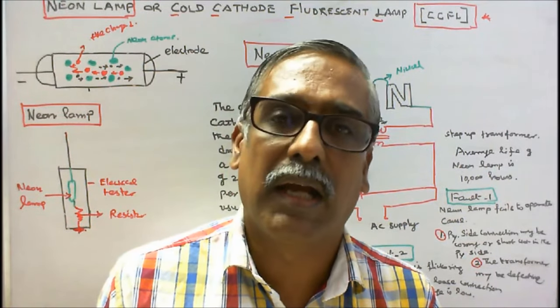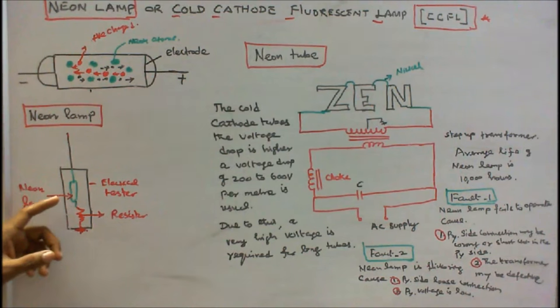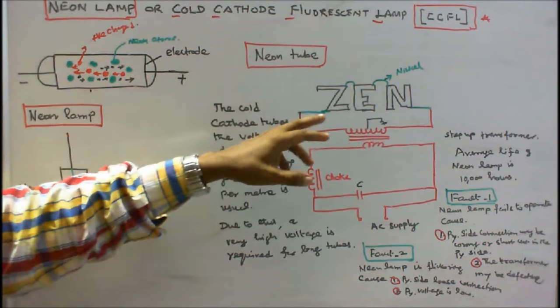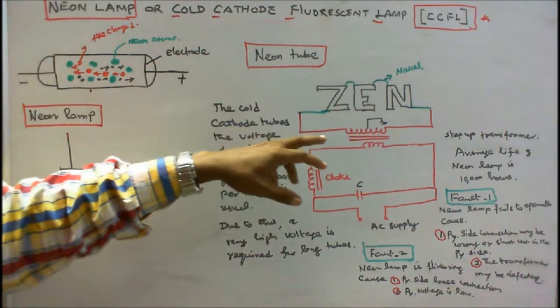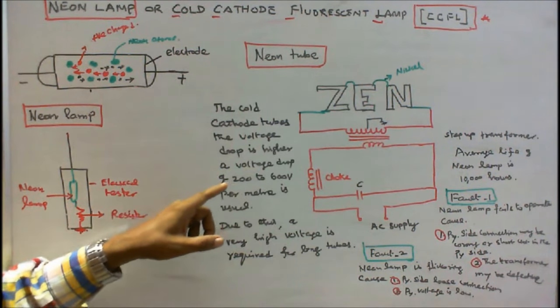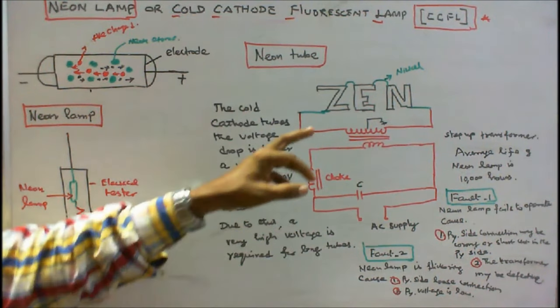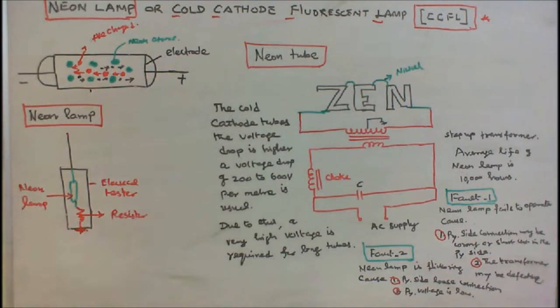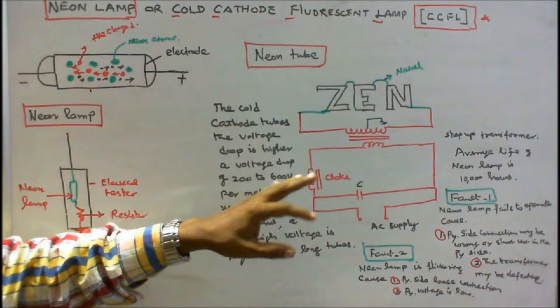Now we see the connection of neon lamps and neon tubes. In the electrical tester, one neon lamp is present and a resistor is connected in series with the neon lamp to minimize the current. For the neon tube, the letters — for example 'ZEN' — are connected with nickel wires to a step-up transformer. In cold cathode tubes, the voltage drop is higher; a voltage drop of 200 to 600V per meter is usual, which is why a step-up transformer is required for long tubes. The average life of a neon lamp is 10,000 hours, and a capacitor is connected on the primary side to improve the power factor.